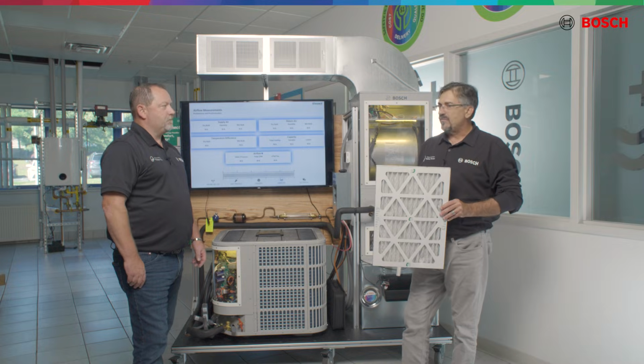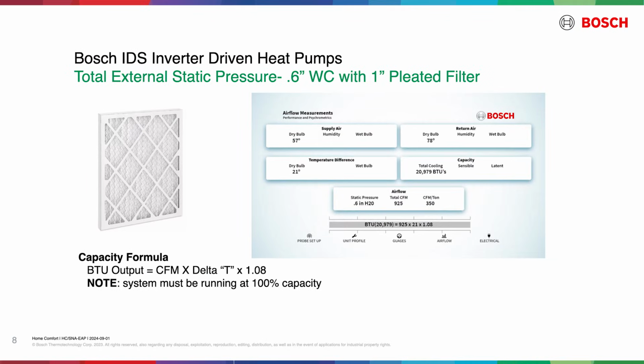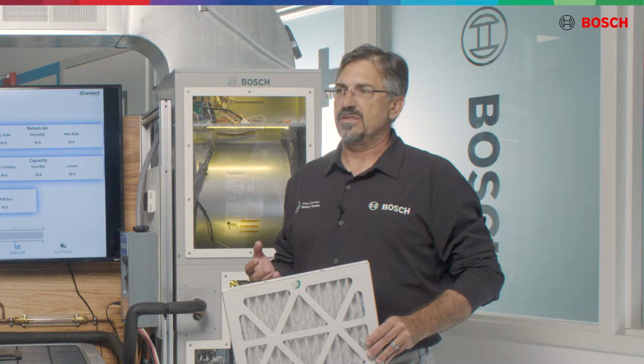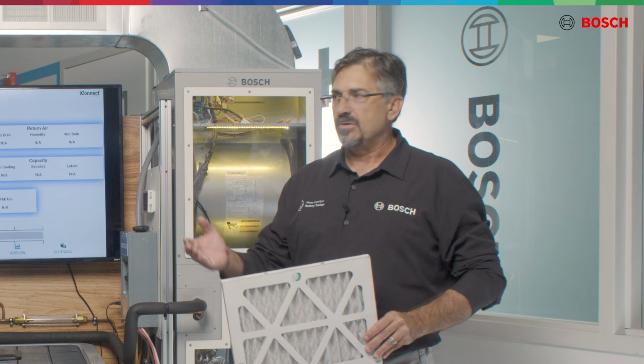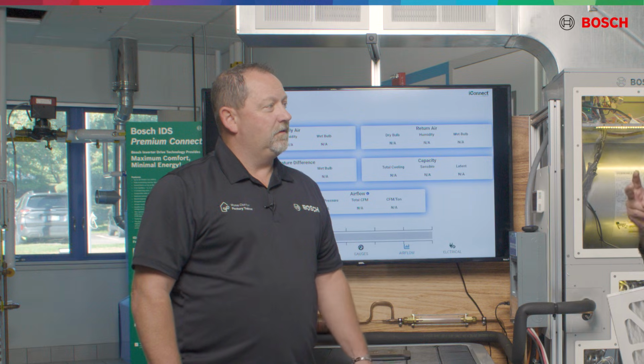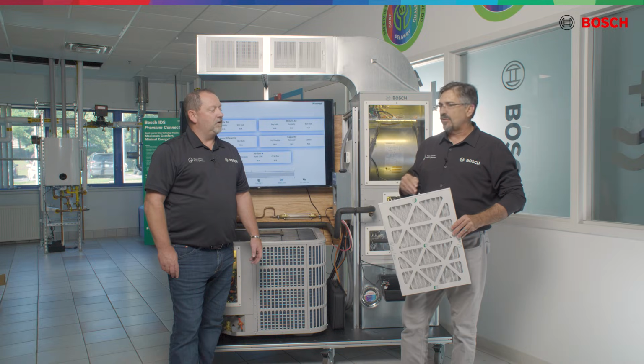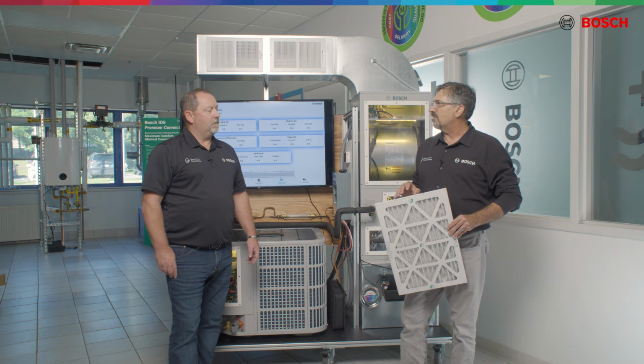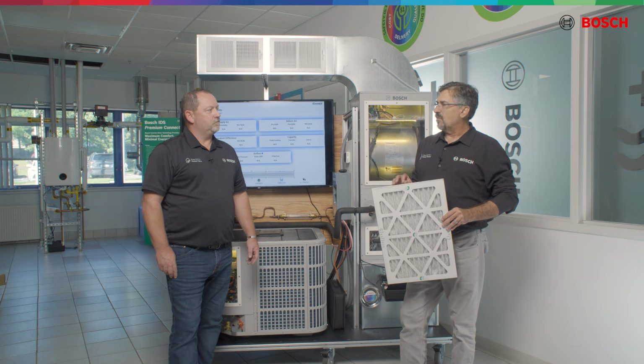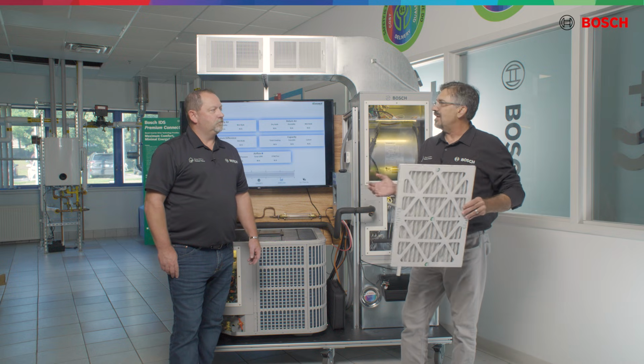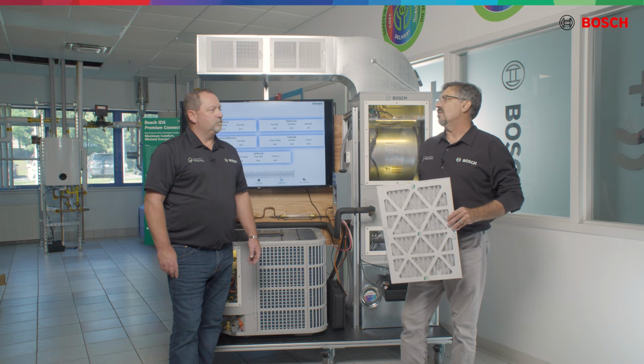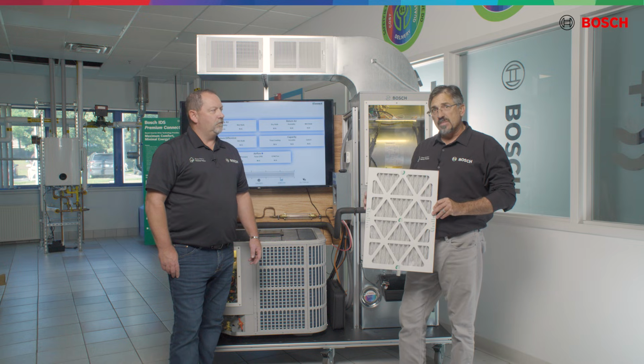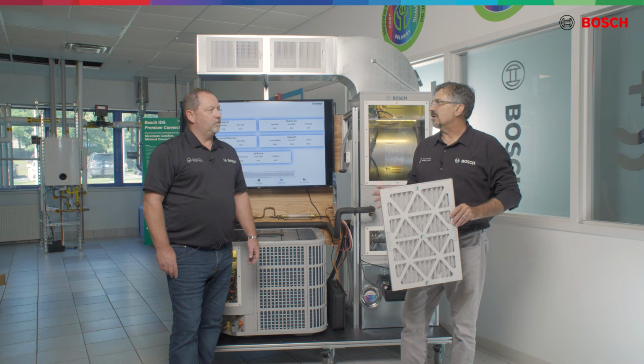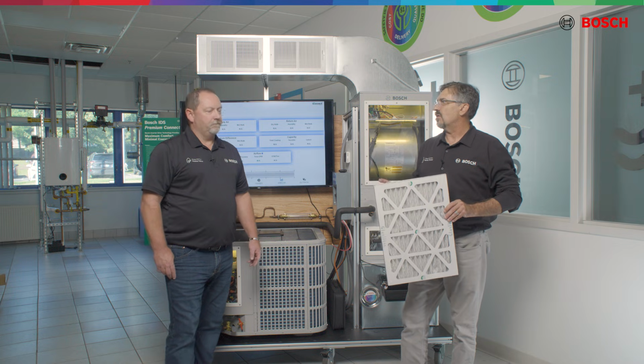The problem is if you have ductwork designed in the 1990s, the 2000s, or even older, therein lies our problem. We had R22 duct systems designed for R22 ductwork, a little bit more forgiving. Chris, we're on our second refrigerant since then. We've gone through 410A. We're into 454. 454 refrigerant still operates the same. We need the correct amount of air moving over our coil. These filters can be installed. You can even use a 4-inch filter, but you must design your ductwork accordingly.